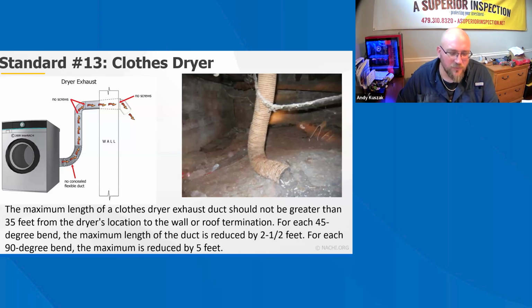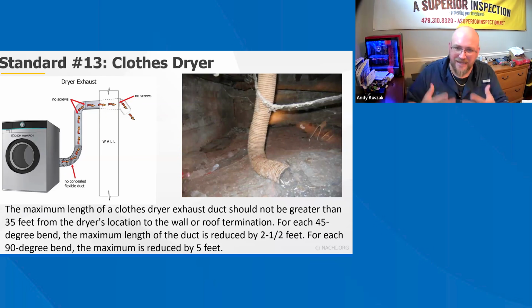You will see all the time where contractors don't really differentiate between bathroom exhaust vent caps and dryer exhaust vent caps. A lot of times they'll just buy in bulk and install them everywhere. So you'll find bathroom exhaust vent caps on dryer exhaust vents. The bathroom exhaust vents should have a screen on them because they are not expelling lint, and you don't want the potential for a bird to make a nest in there and then force that flapper closed.